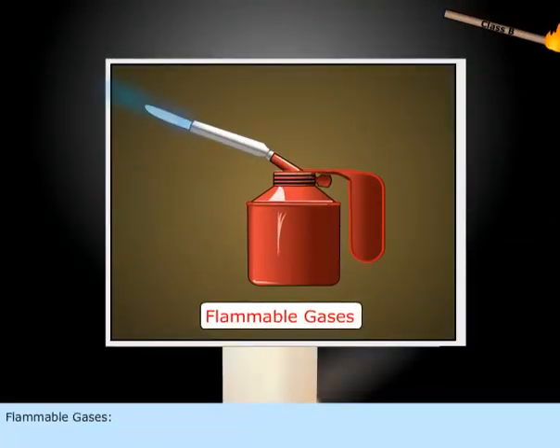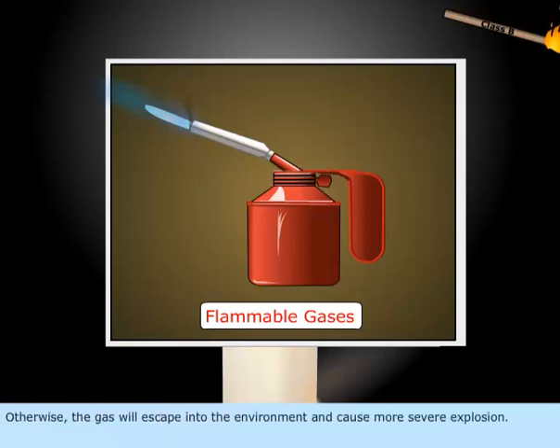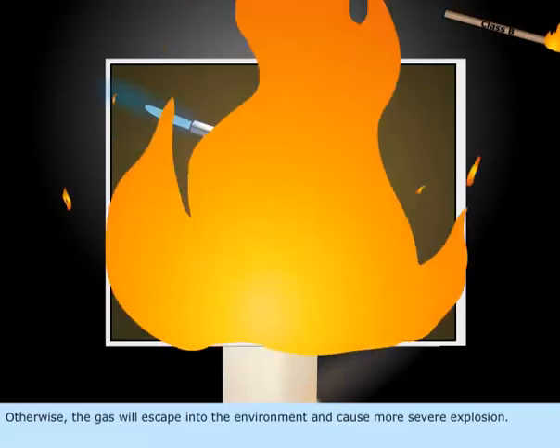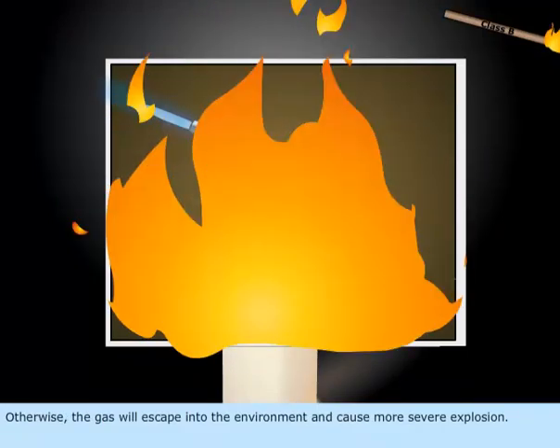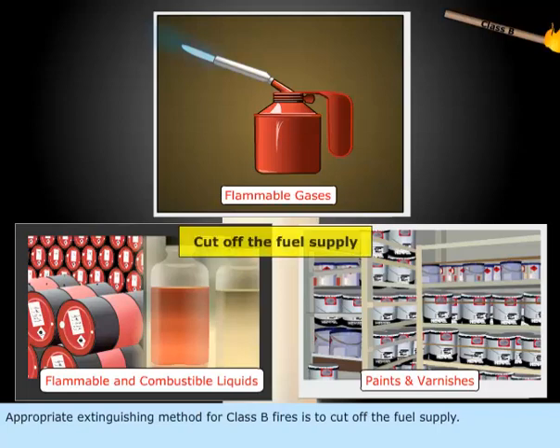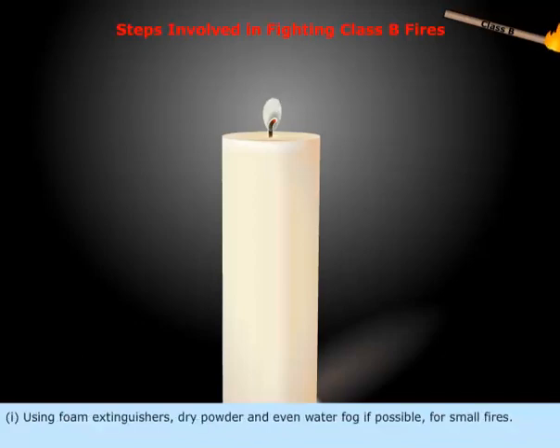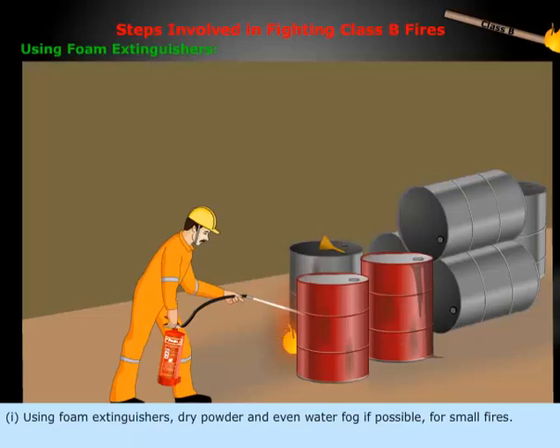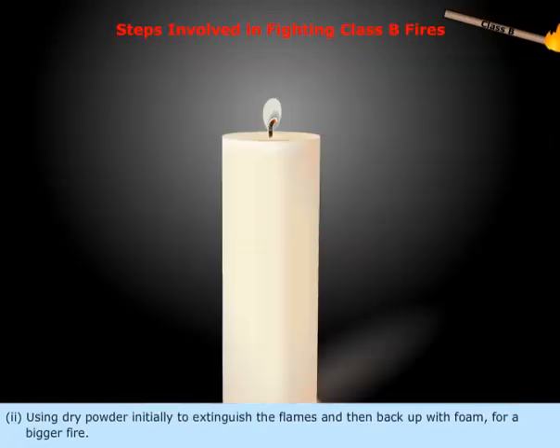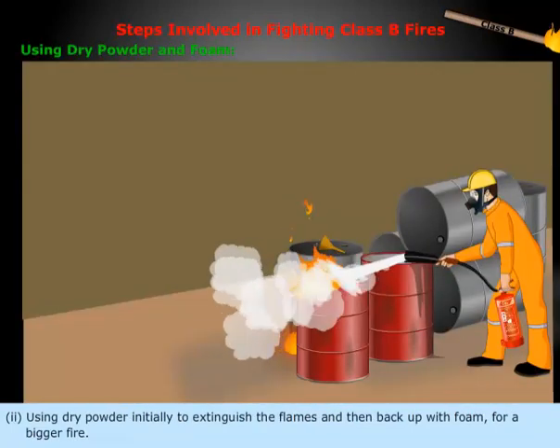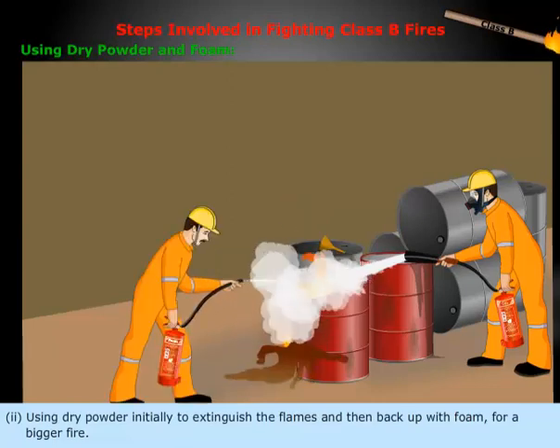Flammable gases: isolate the fuel supply. Otherwise, the gas will escape into the environment and cause a more severe explosion. The appropriate extinguishing method for Class B fires is to cut off the fuel supply. Fighting Class B fires depends upon different situations, but the general steps involve using foam extinguishers, dry powder, and even water fog if possible for small fires. Use dry powder initially to extinguish the flames and then back up with foam for a bigger fire.